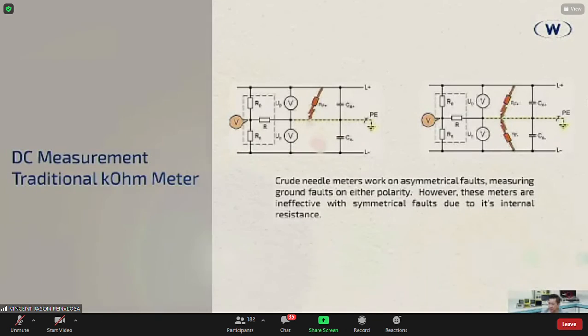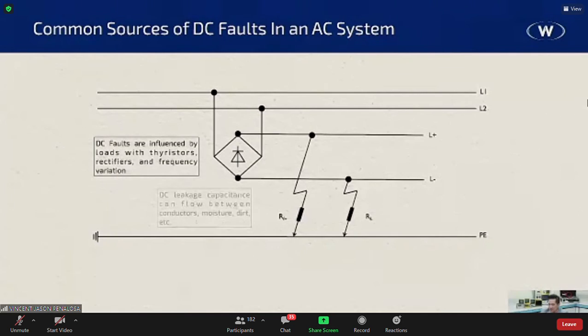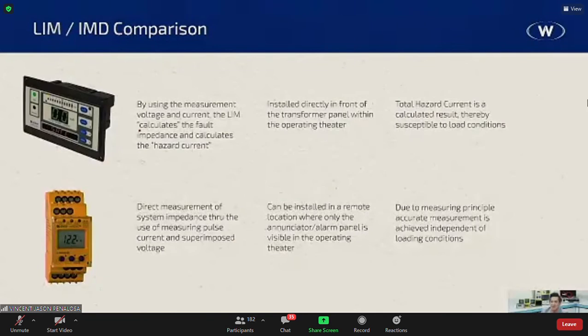No, it can go further than that. So let me just go back to my presentation right here. There you go. So again, it's calculated, no? So that's one of the main problems. You're gonna have that whole panel, and of course, you will have that 60 hertz hum that you will hear inside the operating theater. Also, the total hazard current is a calculated result, thereby susceptible to load conditions, right? Especially if you have the bigger hybrid ORs. That's what they call it nowadays, where you have other equipment in there. So whenever you have other equipment, bigger load equipment, and then you start introducing DC leakage capacitance as well.